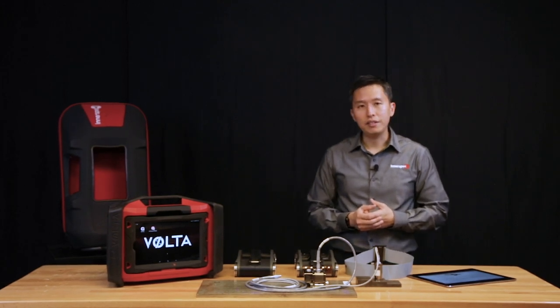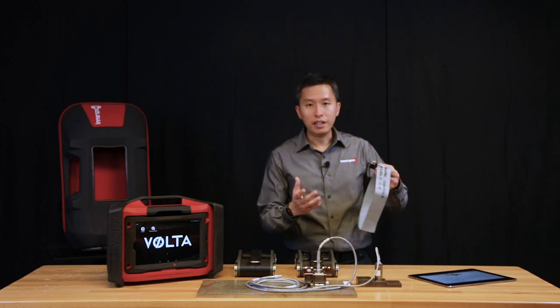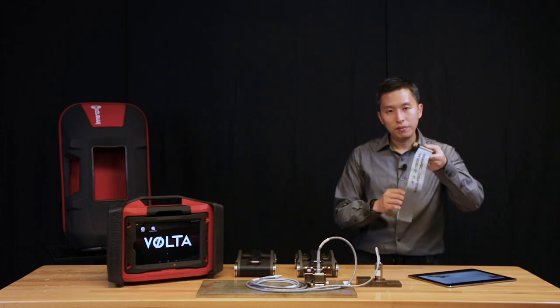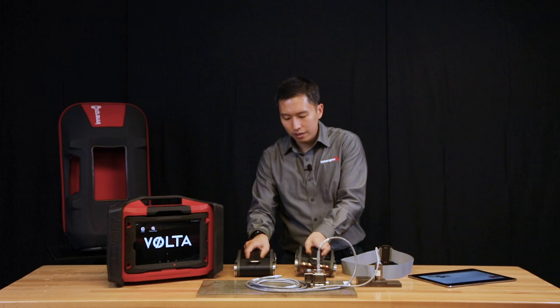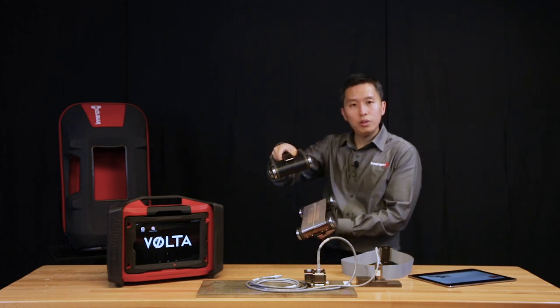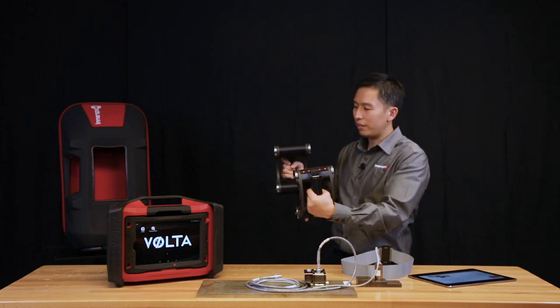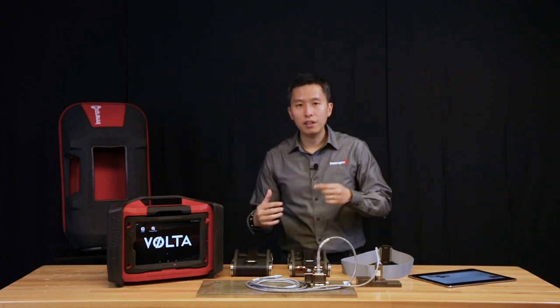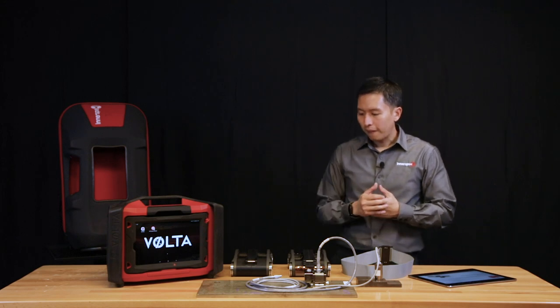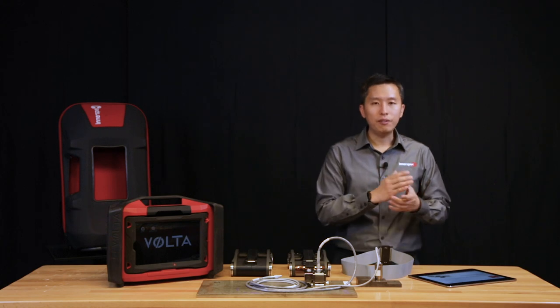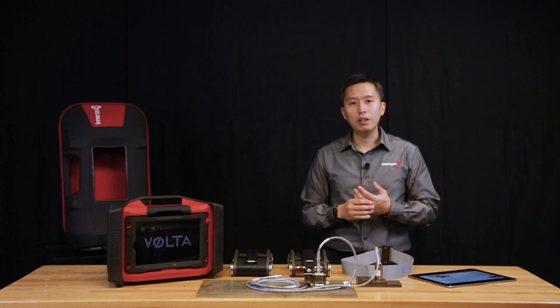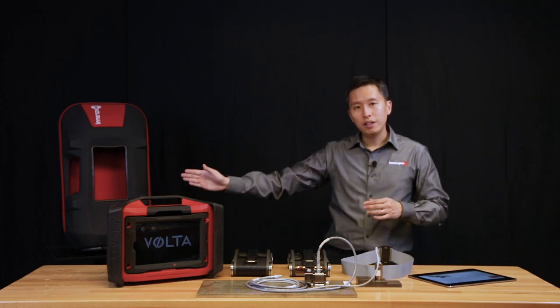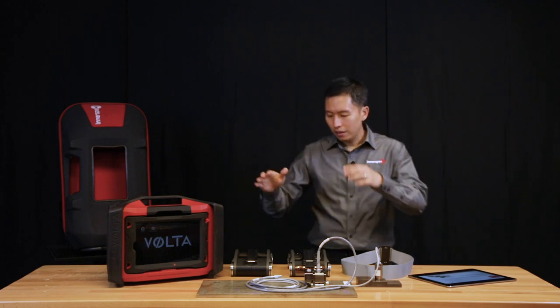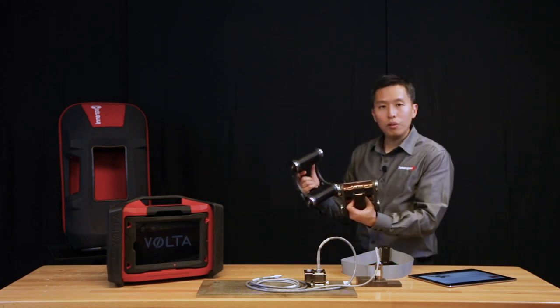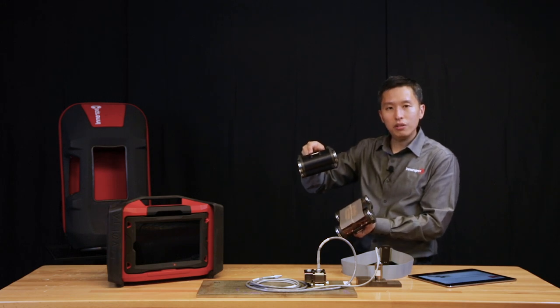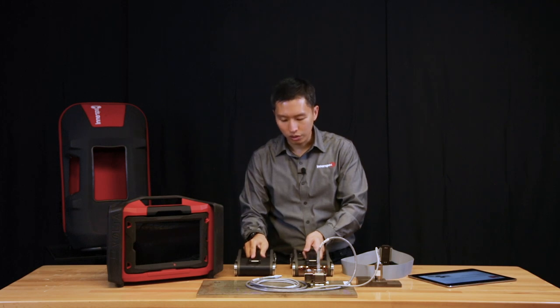The next mode of inspection is known as the synthetic focusing technique, or synthetic focusing inspection. It uses the ribbon collar to transmit sound and a motorized scanner that we are currently prototyping to receive sound. When the motorized scanner moves, it provides good circumferential resolution as well. In the calculation that we have made, it is shown that for an 8-inch pipe, we can have a circumferential resolution down to 9 degrees. So it is not only providing very good axial resolution for a long-range UT technique, it also has very good circumferential resolution, which is a breakthrough in the long-range UT realm.